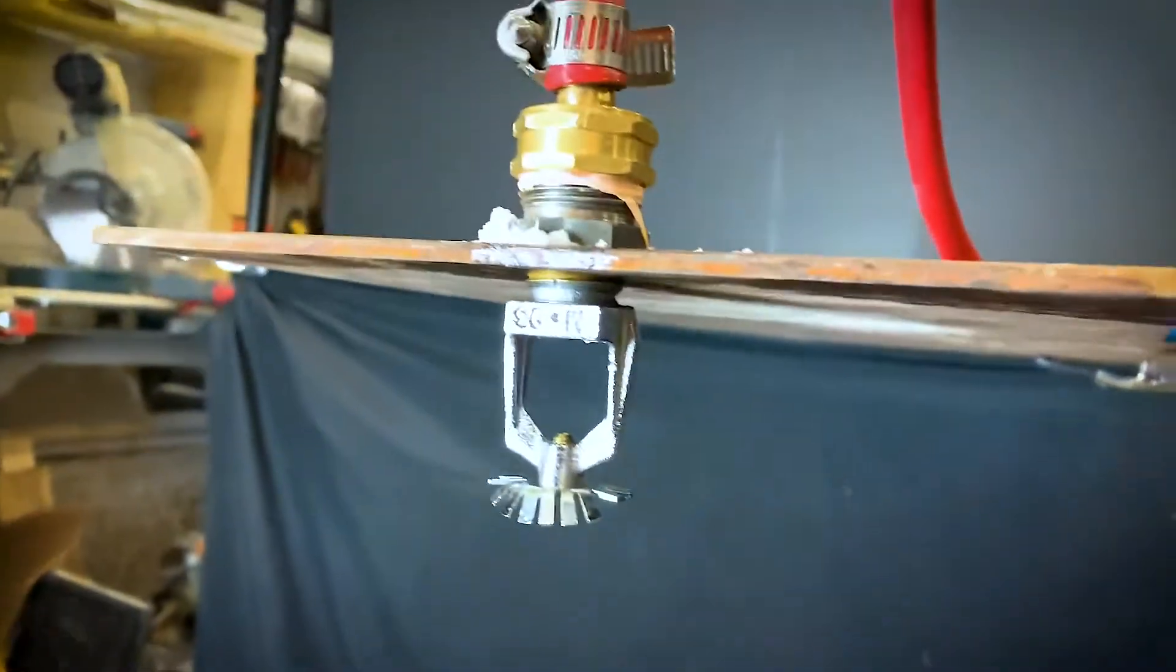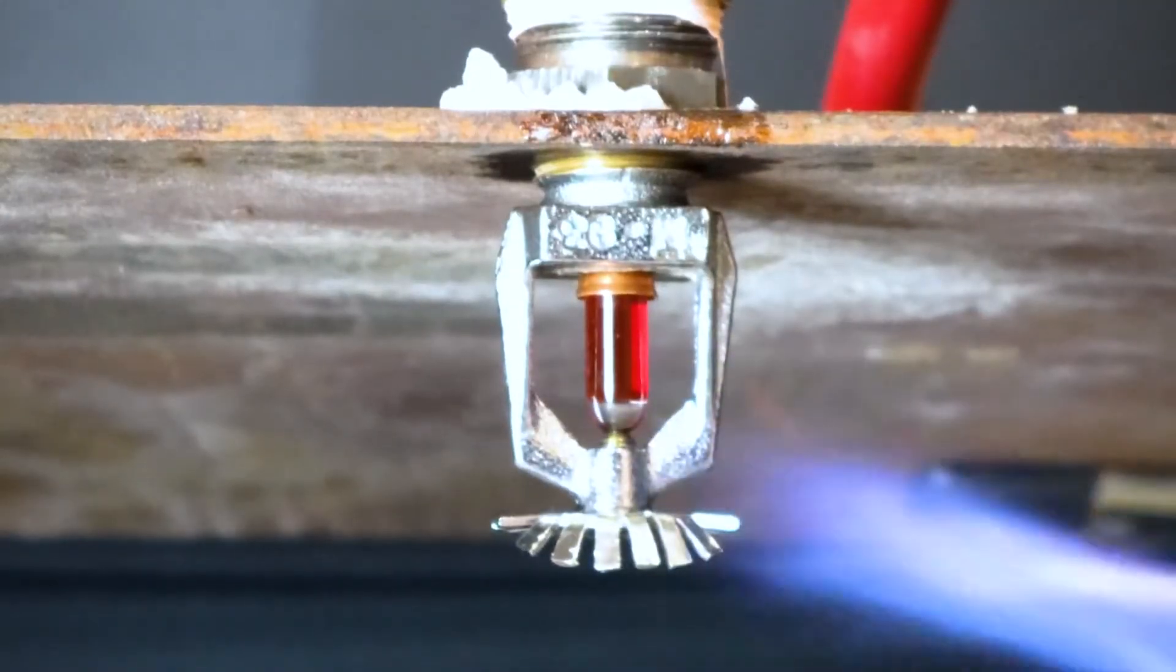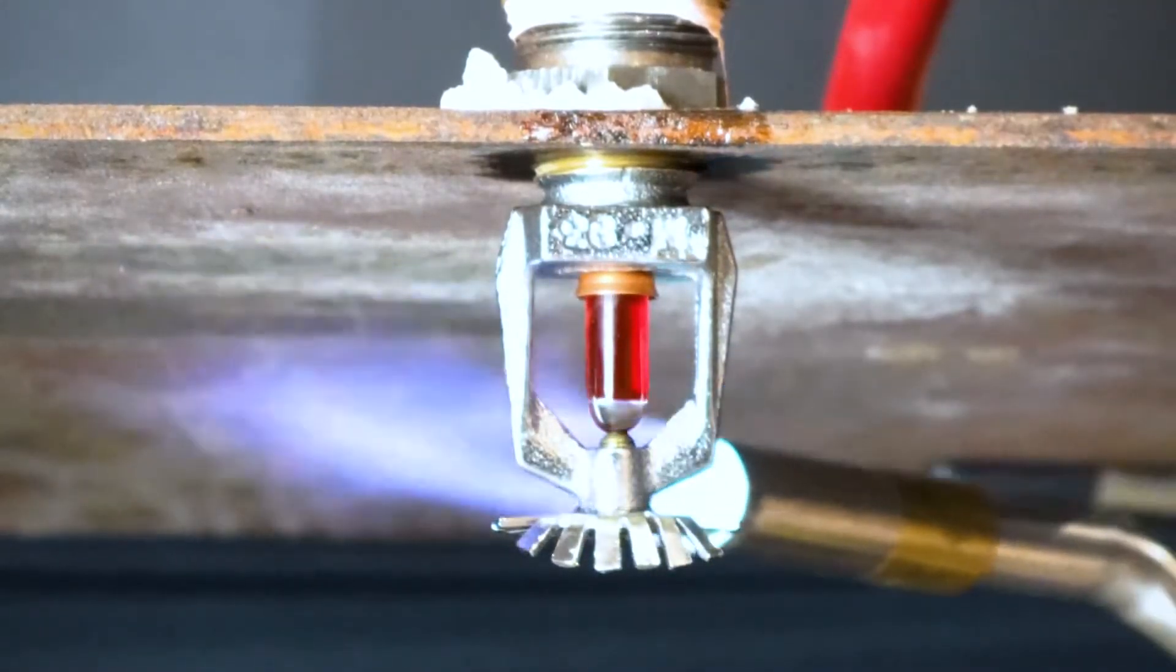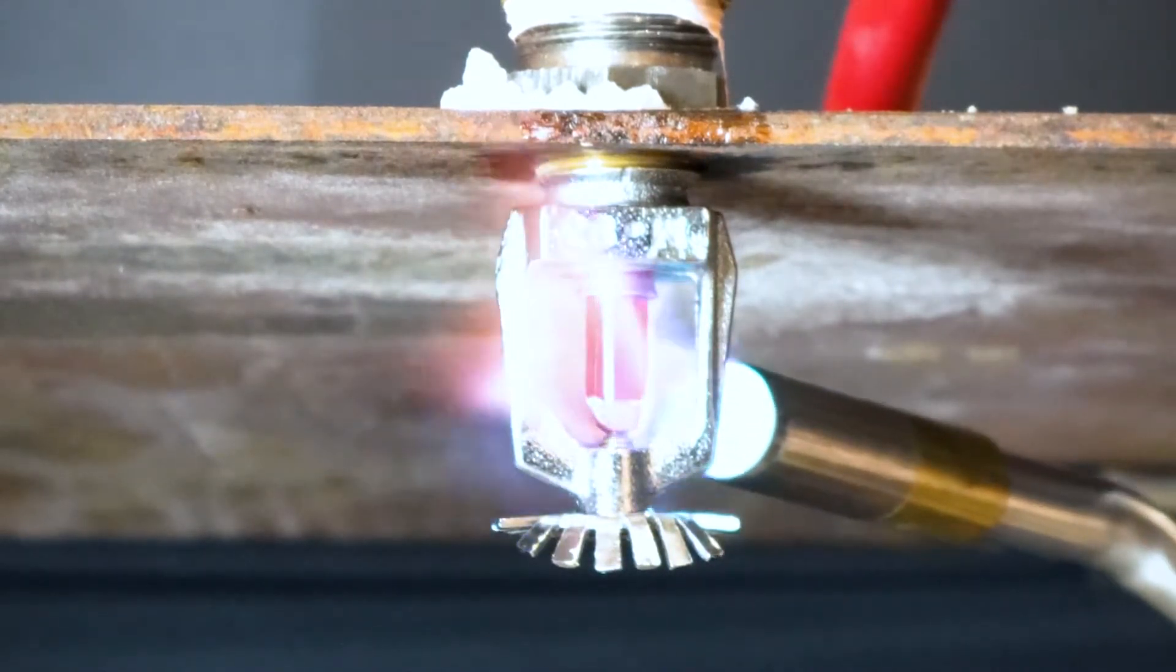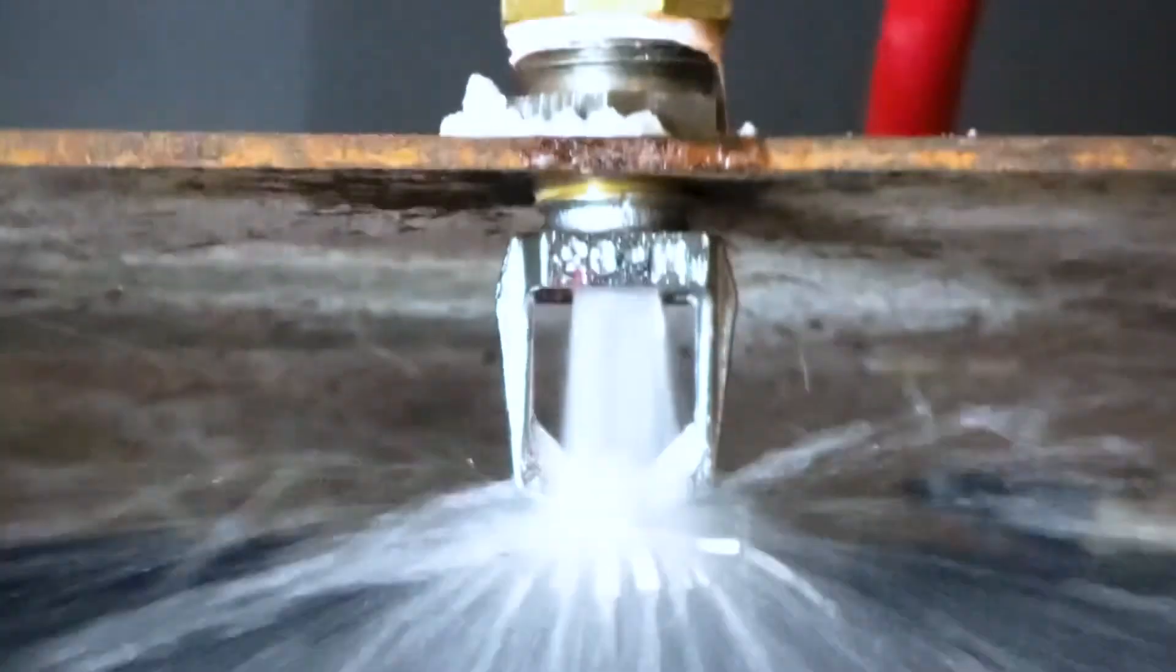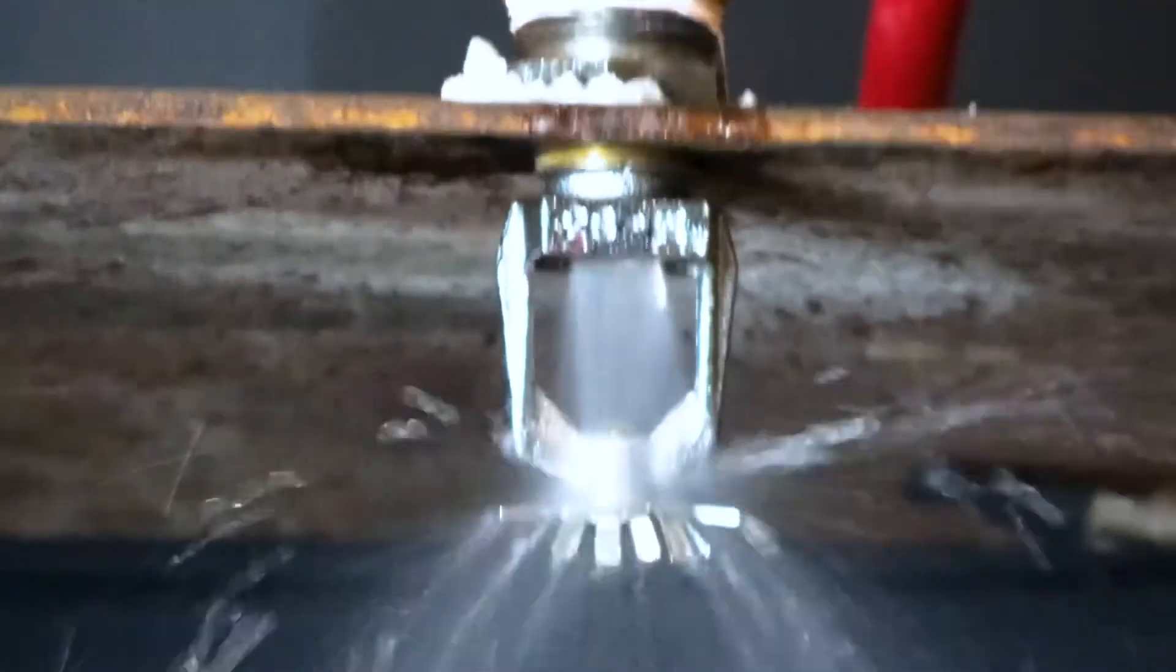So let's dive in and take a closer look. When a fire reaches the sprinkler head, the flame will heat up the liquid inside this little glass bulb, causing it to expand and then shatter the glass. And once it shatters, as you can see, the water sprays down and the little fan underneath will disperse the water within the coverage area of the sprinkler head.